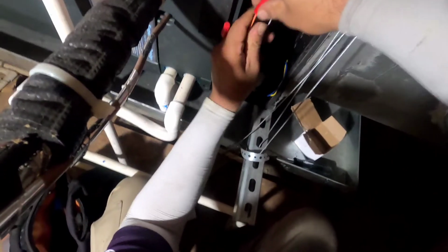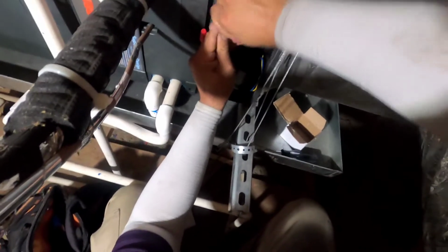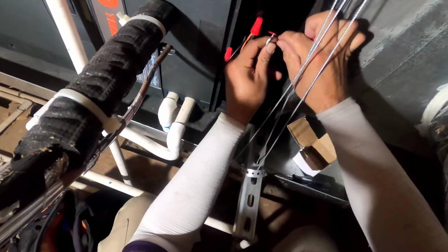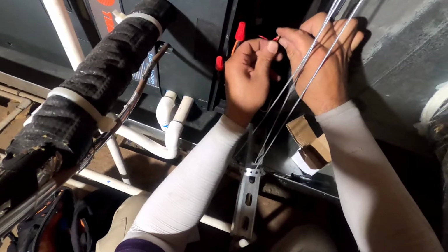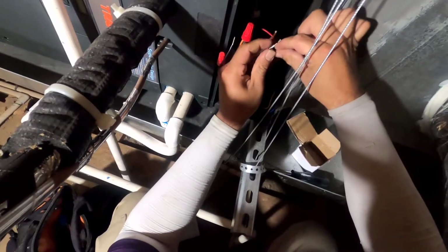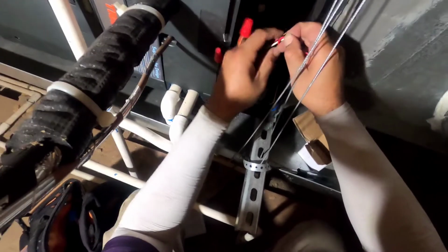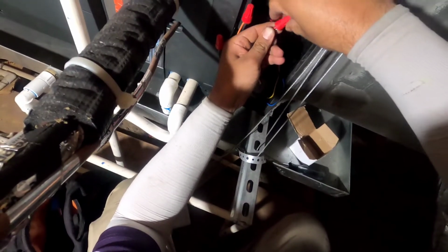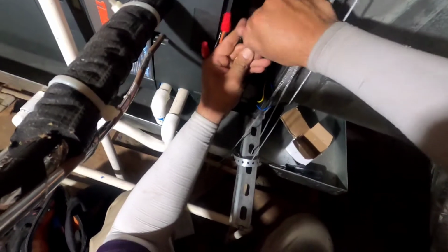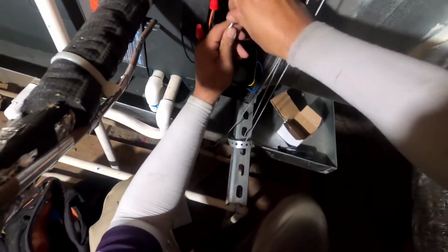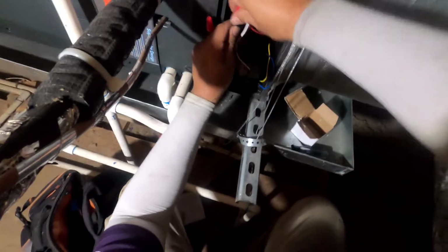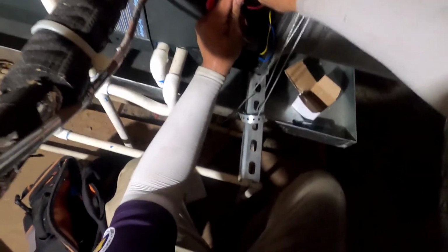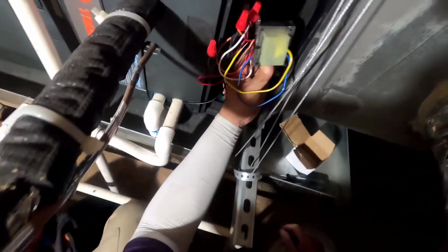So go ahead and put that on, just get that in there, squeeze it nice and tight, and then our white, which is our common, is going to go to the other leg of incoming voltage. So now we're doing that, and then we put our wire nut on there. Really good. Give it a little bit of a pull on there, just to make sure it's snug and staying on there. So now let's go ahead and mount the transformer somewhere.